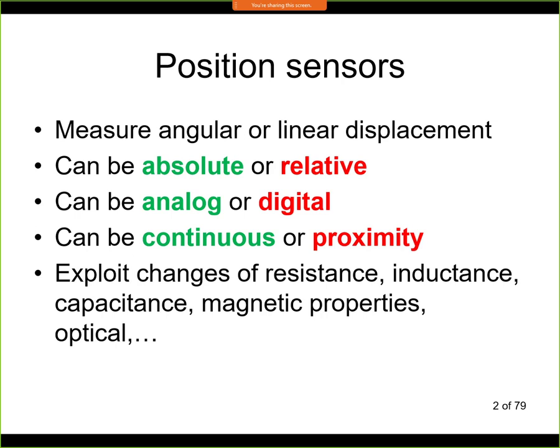A rule of thumb for absolute and relative sensors is about a factor of 10. So if an absolute sensor has 4,000 positions per some range, the relative sensor may easily have something like 100,000 positions per the same distance. The relative sensor is typically much more accurate with smaller resolution for the same price, but it requires you to manually zero the position. The absolute sensor gives you correct position after power-up; a relative sensor requires you to go to some zero position.